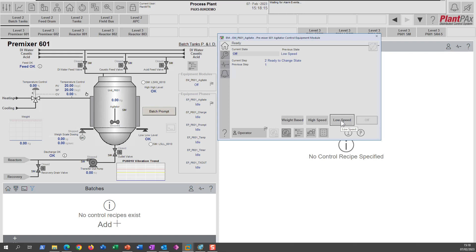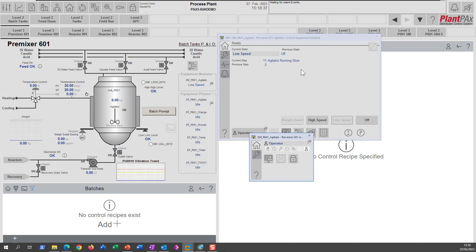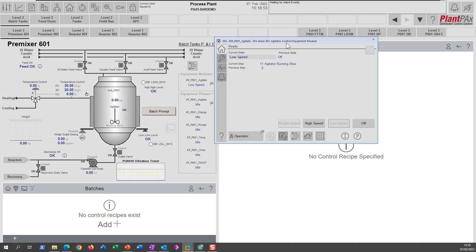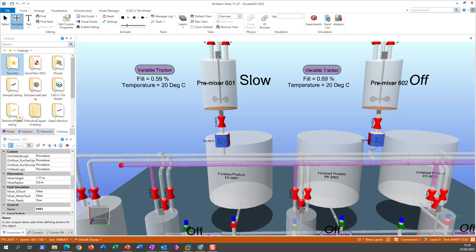Let's go into the low speed state by selecting the low speed button. All the buttons become disabled while the equipment module transitions, and once it's ready to move to a different state, the available states become enabled. We can now see that from low speed we can only go to off or high speed. The agitator is running slow, and the equipment module's sequence logic inside the controller has told the agitator to go into the running slow state. Switching to Emulate 3D confirms the agitator is running in slow mode.